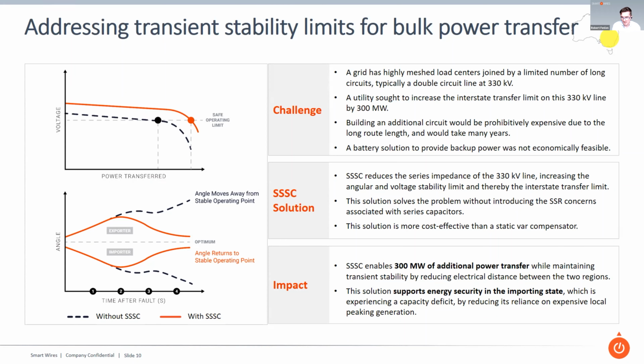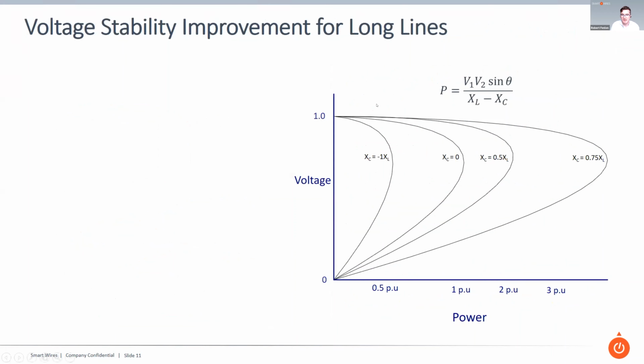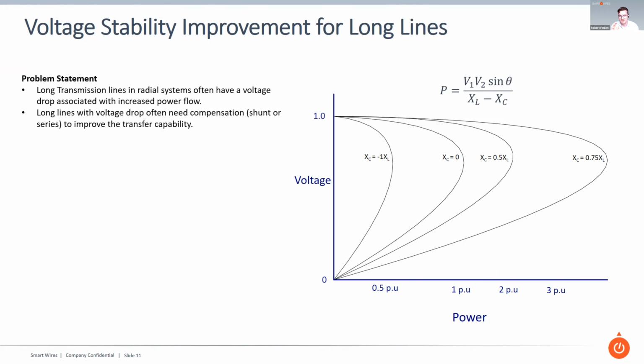The impact that this studied solution would have is it was going to increase the transfer capacity by 300 megawatts, and also reduce the dependence on local peaking units, and reduce the cost of electricity in the demand center region. And then looking specifically at how this works, on the right hand side you have that curve showing the relationship between the transferred power and the voltage. The level of compensation here is shown as XC. As you increase the level of compensation, you push the nose of that curve out and can increase the transfer capacity of that line. So the problem statement here is that these long lines end up with a limit where you have either a drop in voltage or the voltage pushed into an unstable region as you try to push more power down that line.